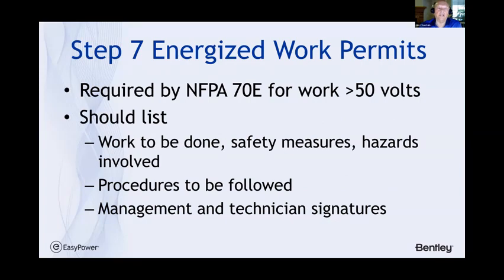Step 7 is energized work permits. I pause because it's difficult for people to understand that this is not something that should be considered a burden. It's required by NFPA 70E for work over 50 volts, and it should list the work to be done, the safety measures involved, and procedures to be followed, and primarily make sure that management and technicians sign the work permit, to include or verify that we have management support for workers to be put in an elevated hazardous situation.